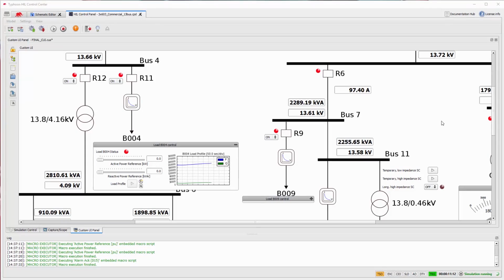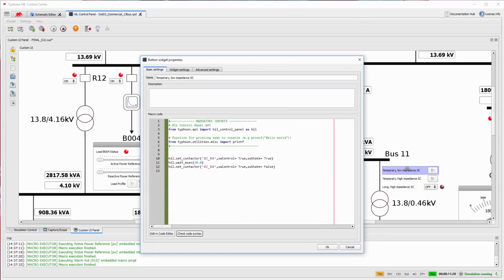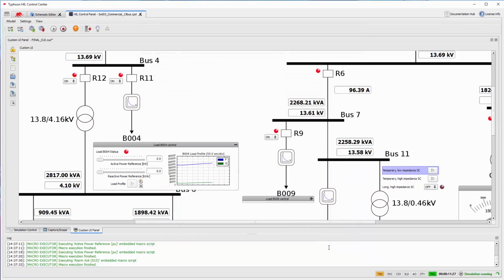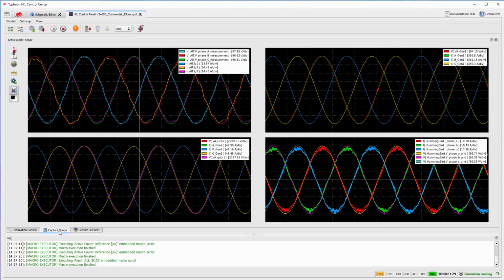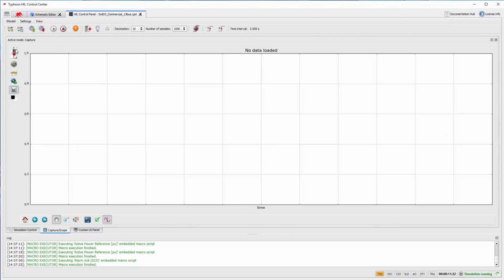For the first scenario, we implemented three types of short circuits. Two temporary, one with high impedance and one with low impedance, and a permanent high impedance phase-to-phase fault. To execute the temporary short circuits, we use the button widget that will close the contactor that ties two phases together and reopens the contactor 30 milliseconds later. To capture the event waveforms, we use our capture tool and set the trigger as the state of the short circuit contactor. Once it changes to closed, the system recognizes the trigger and captures all the waveforms set with the decimation and number of samples defined before.